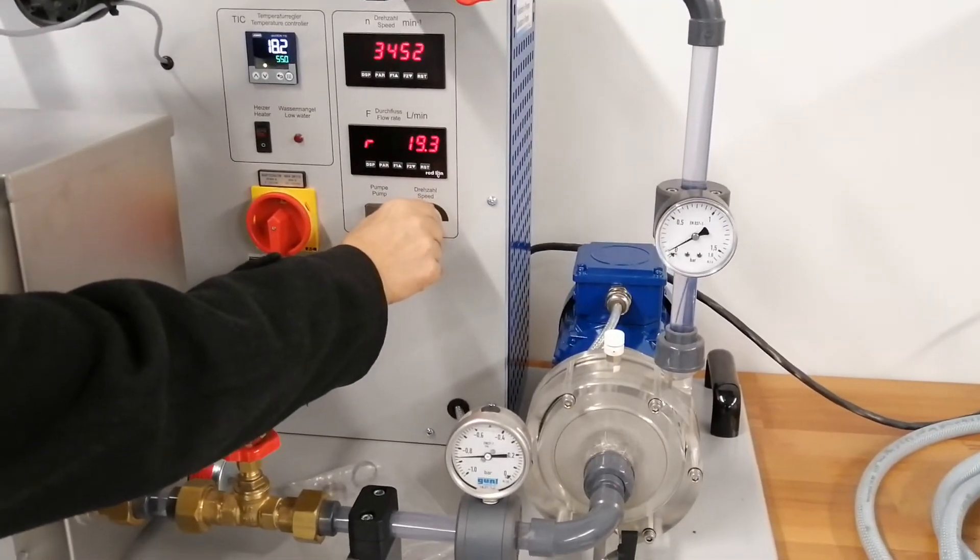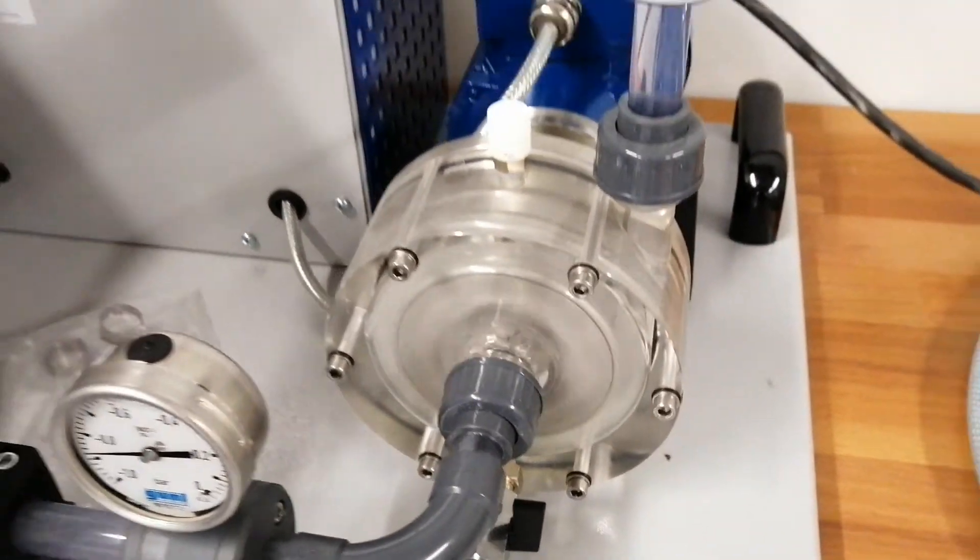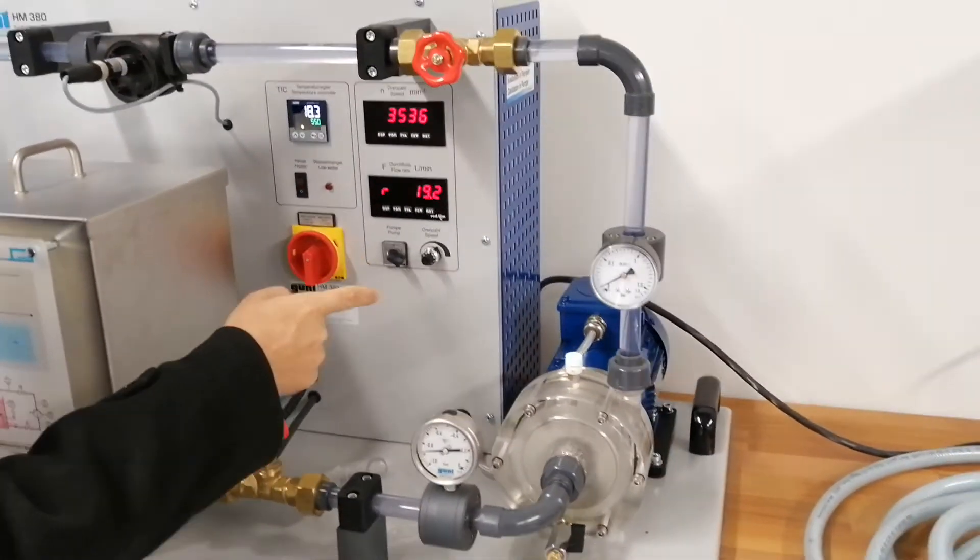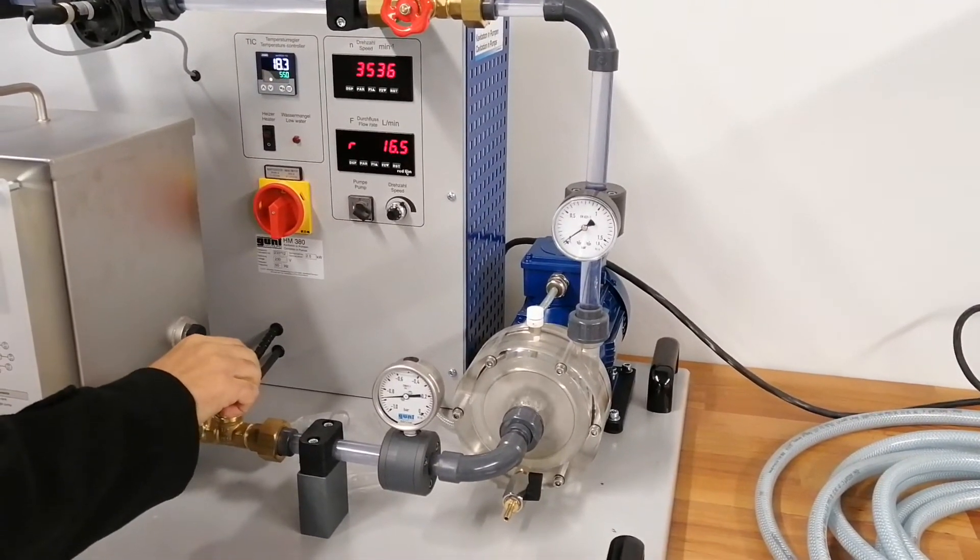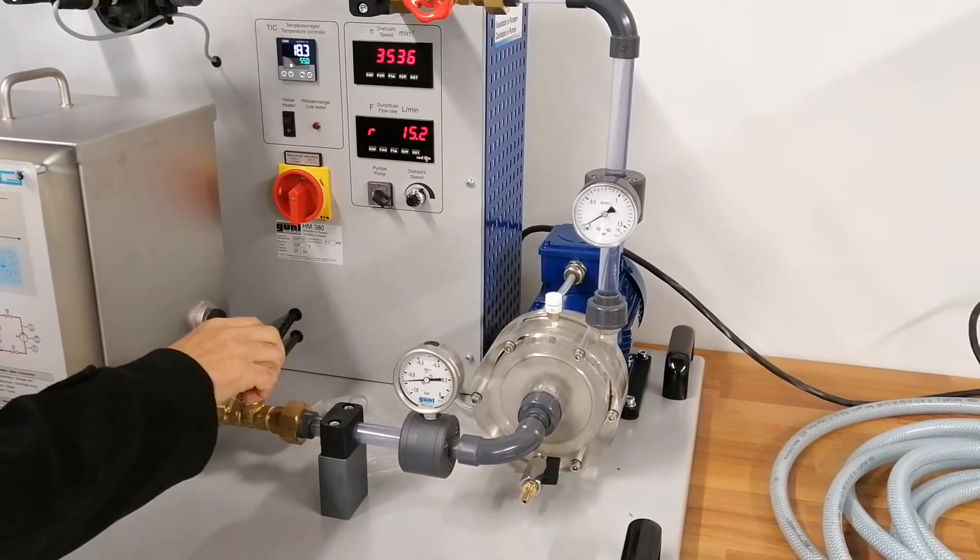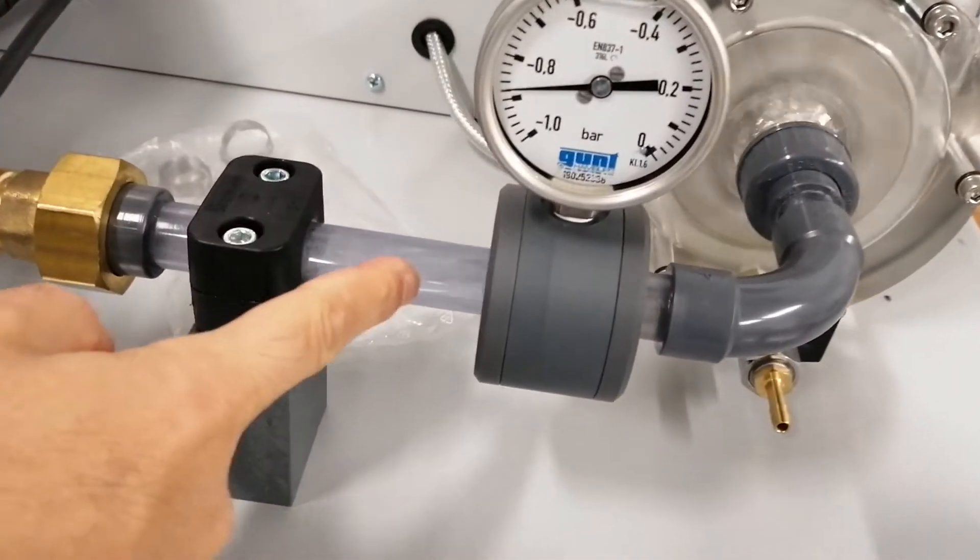If you see here, I increase the speed and you see increased cavitation. Increased pump speed means increasing cavitation. There is also here, you can see some problem here.